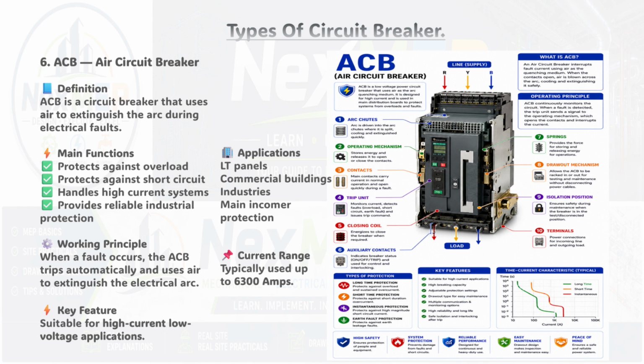ACBs are commonly used in LT panels, main distribution boards, commercial buildings, industries, and as the main incomer protection in large facilities. The typical current range for ACBs goes up to 6,300 amps, so this is a very powerful breaker. One standout feature is the draw-out mechanism, which means you can pull the breaker out for testing or maintenance without disconnecting the power cables. That's really useful in live industrial environments.